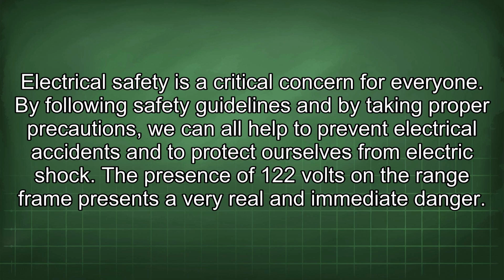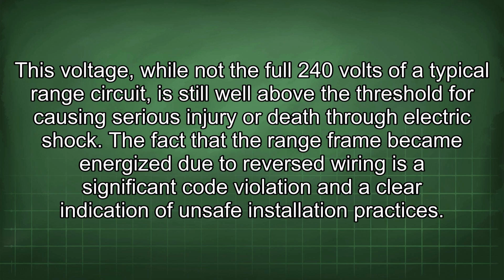The presence of 122 volts on the range frame presents a very real and immediate danger. This voltage, while not the full 240 volts of a typical range circuit, is still well above the threshold for causing serious injury or death through electric shock. The fact that the range frame became energized due to reversed wiring is a significant code violation and a clear indication of unsafe installation practices.